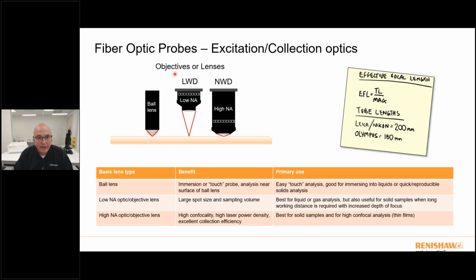The last thing I'll say about this slide really is that when you're choosing these long working distance optics with lower NAs, there's sometimes a benefit there because that lower NA is going to give you a larger depth of focus, and that makes it a little bit more forgiving for quality of focus on the sample, especially if you're doing handheld fiber probe analysis. Then you want to have some sort of depth of focus there so that the quality of focus isn't necessarily affecting the quality of the Raman data. So if you have a lot of surface variation, then a lower NA optic may have some benefit to you.